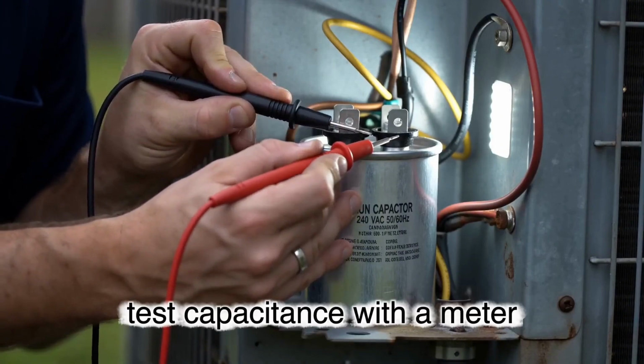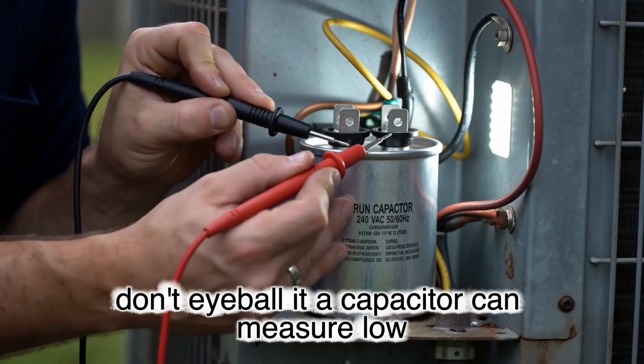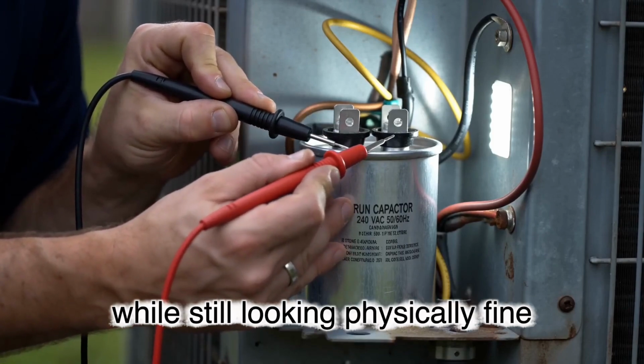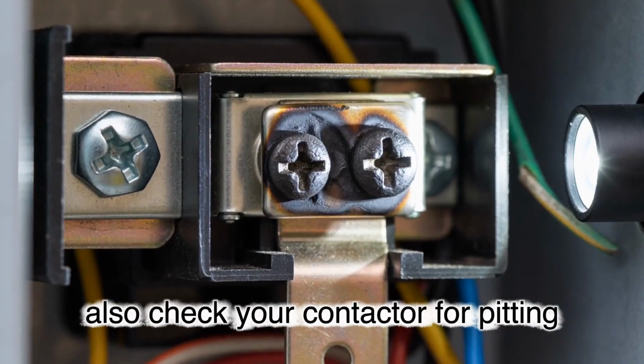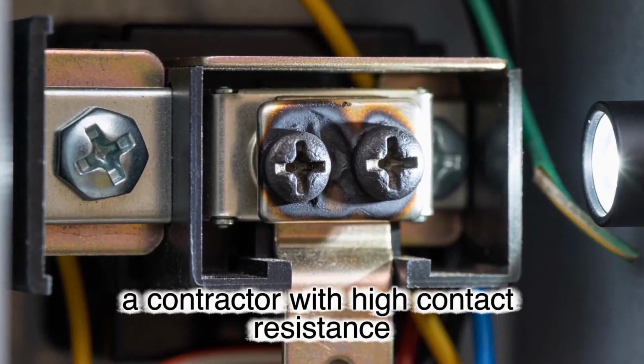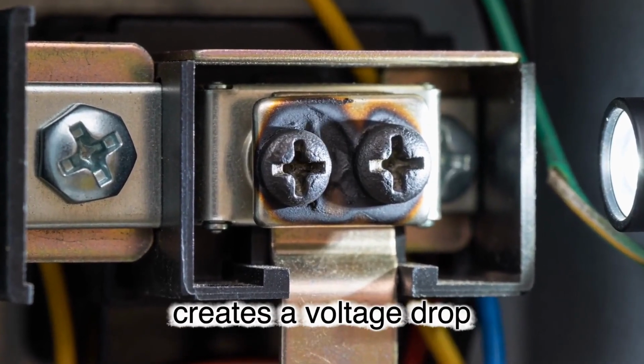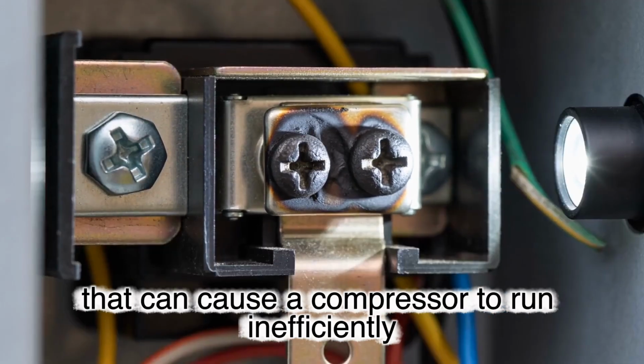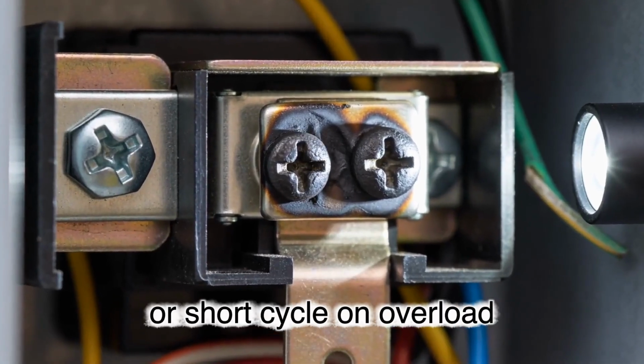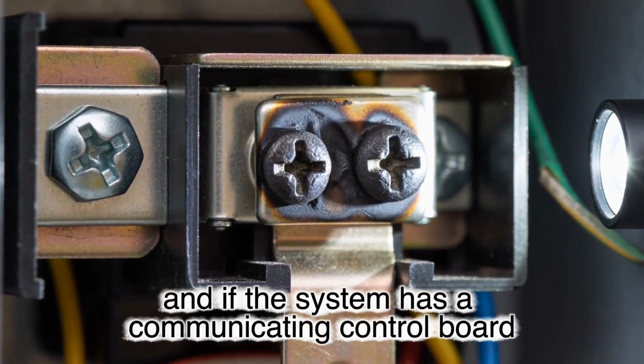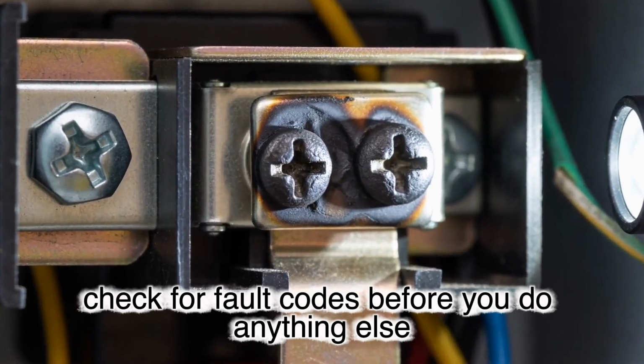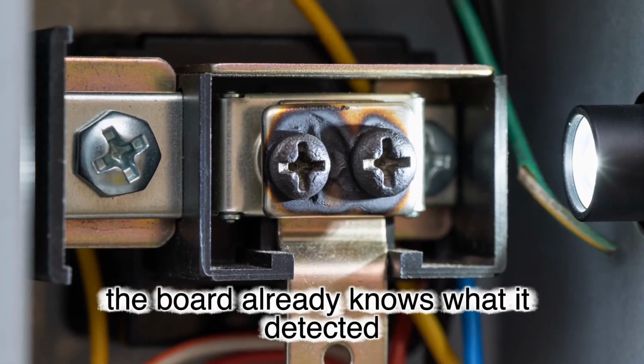Test capacitance with a meter. Don't eyeball it. A capacitor can measure low while still looking physically fine. Also check your contactor for pitting or burning on the contacts. A contactor with high contact resistance creates a voltage drop that can cause a compressor to run inefficiently or short cycle on overload. And if the system has a communicating control board, check for fault codes before you do anything else. The board already knows what it detected.